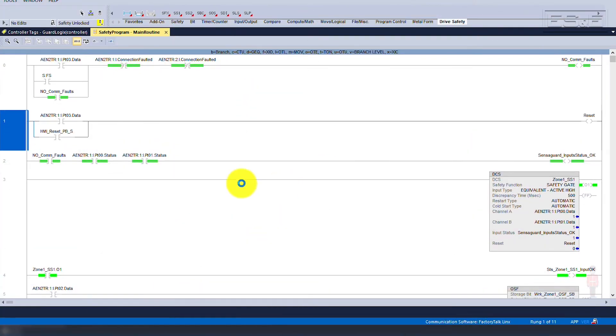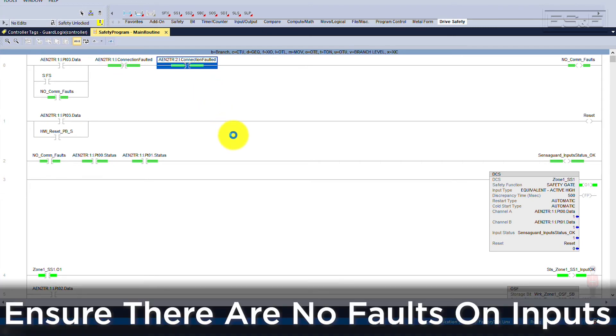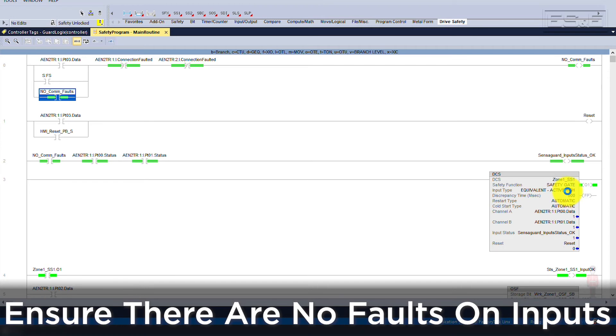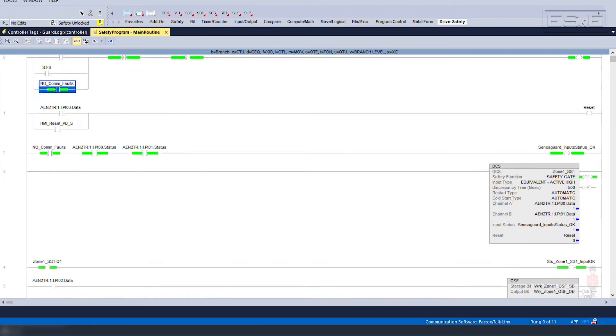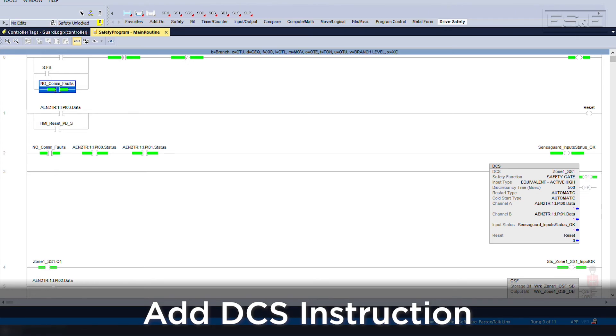Now that the system is configured and wired, we can review the code necessary to make this a functional circuit. The first thing that we need to ensure is that there are no faults on either of the safety input channels needed for the circuit. Now that we have verified no faults exist, you can feed a DCS instruction with the safety function of door guard, an input type of equivalent active high, a discrepancy time of 500 milliseconds, and a restart type of automatic.